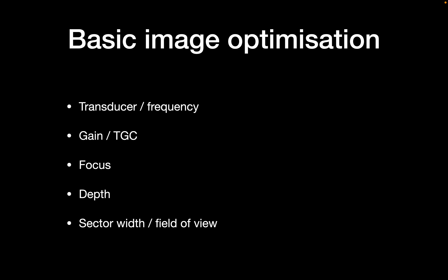First, you'll have to select the right transducer for whatever you're imaging. Some types of transducers are better for abdominal imaging, while other probes are better for vascular imaging. If there's an option to select different frequencies for that probe, you'll have to think about that and change the frequency accordingly. Once you have your image, you'll need to set your overall gain, or use time gain compensation, to decide the brightness or whiteness of your image.